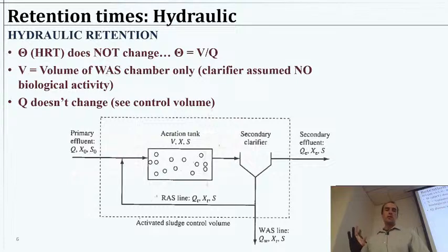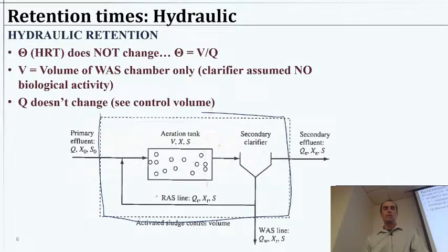So hydraulic retention time is not going to change if we change the recycle. And the reason for that is we have the same volume, and we're looking at the control boundary out here. The V over Q is going to be the V over the Q that is crossing this control boundary. You might say to yourself, well, aren't we speeding up the water that's going through here when we recycle? Well, yes, but that water is recycled. It's already been in there once.